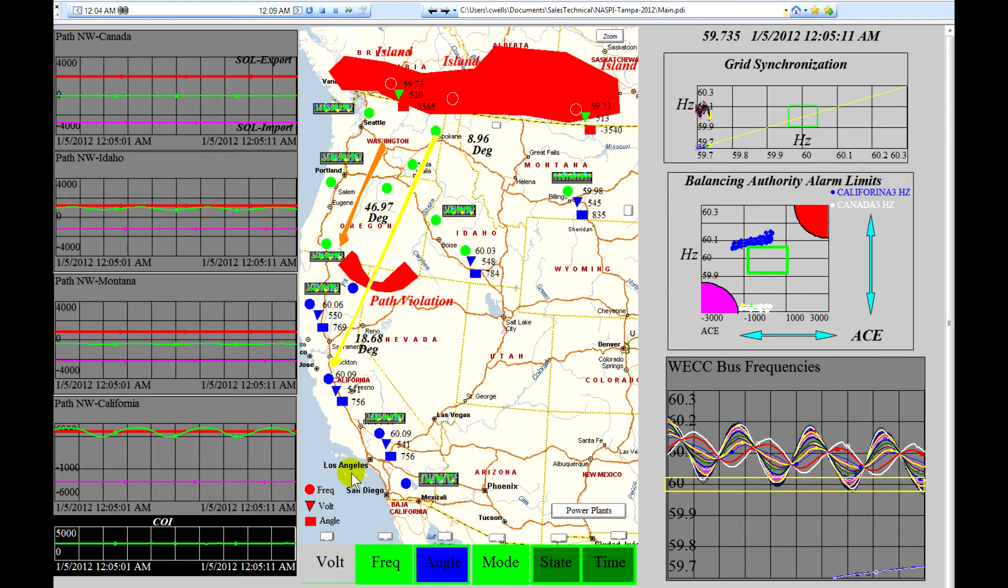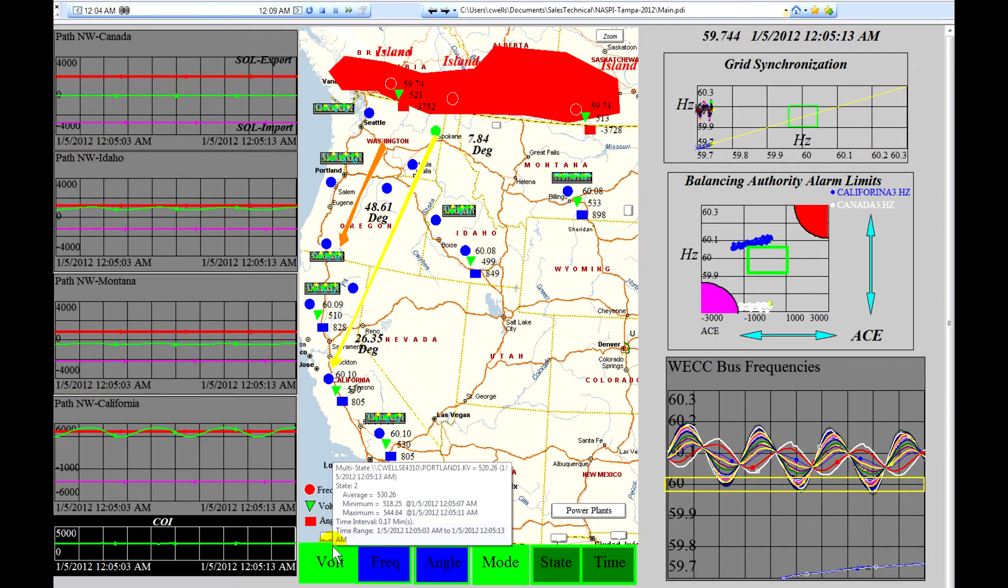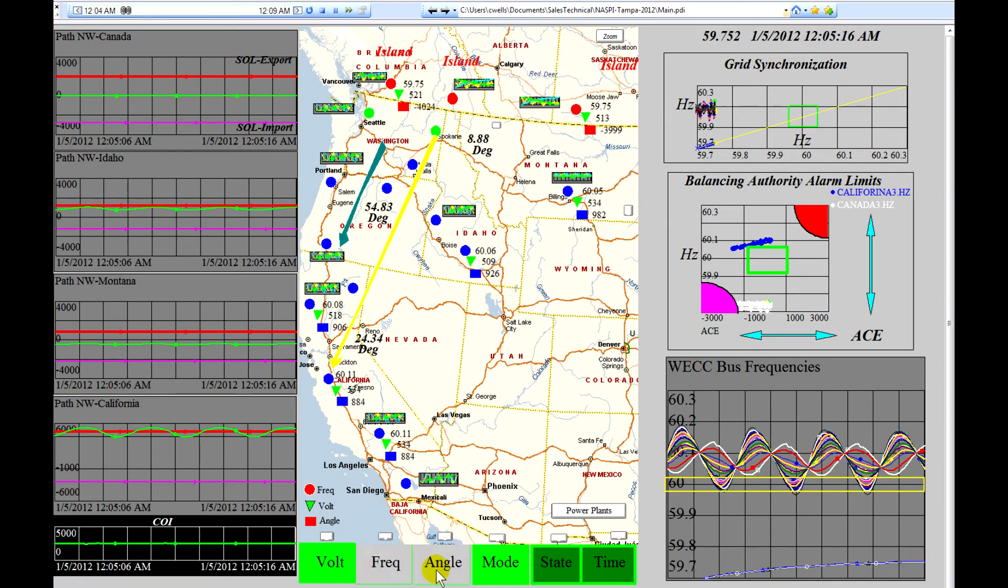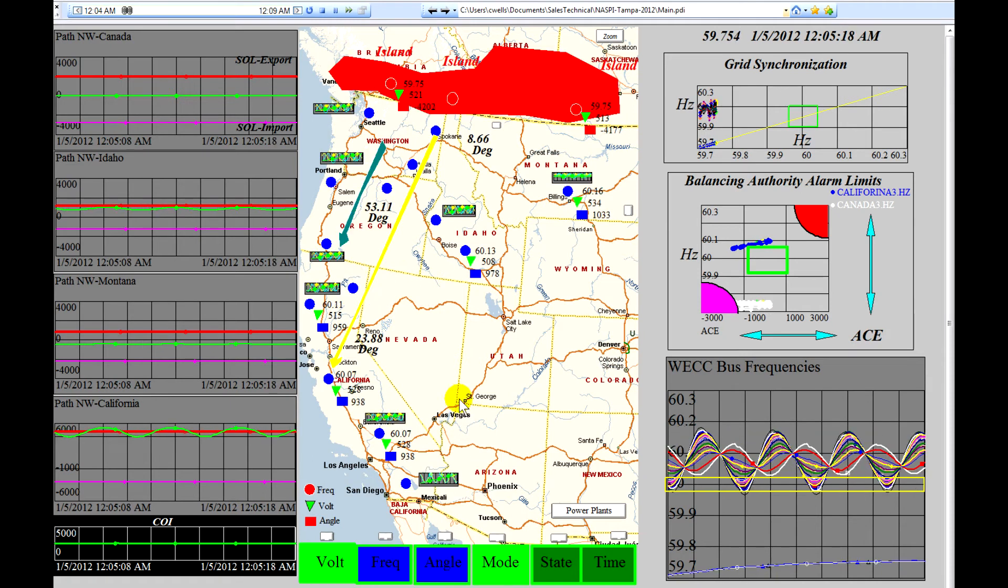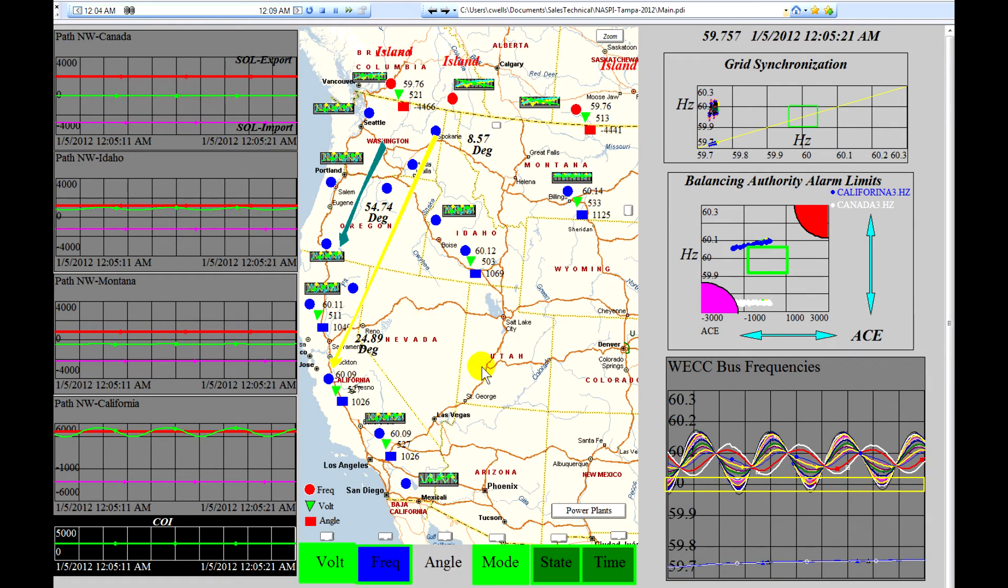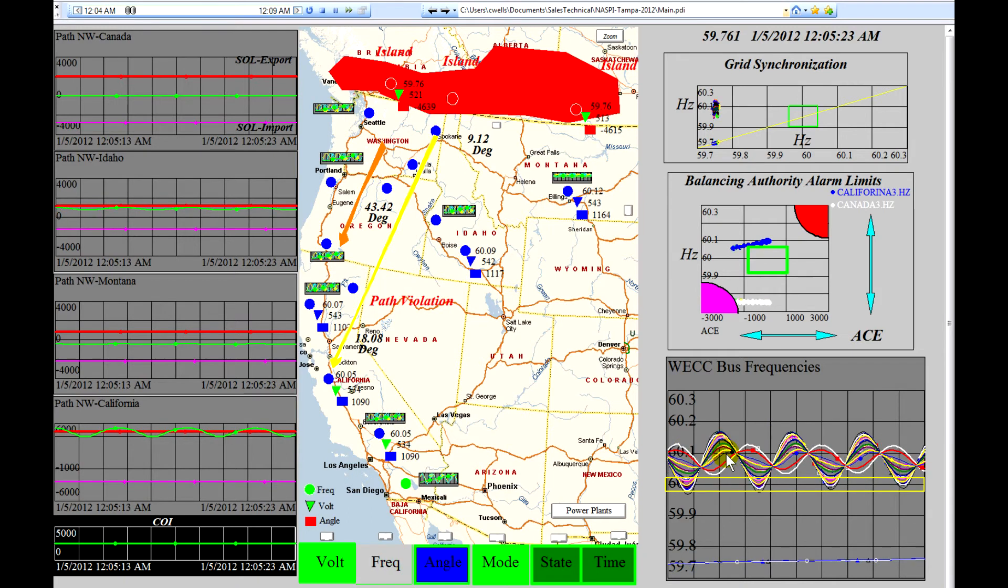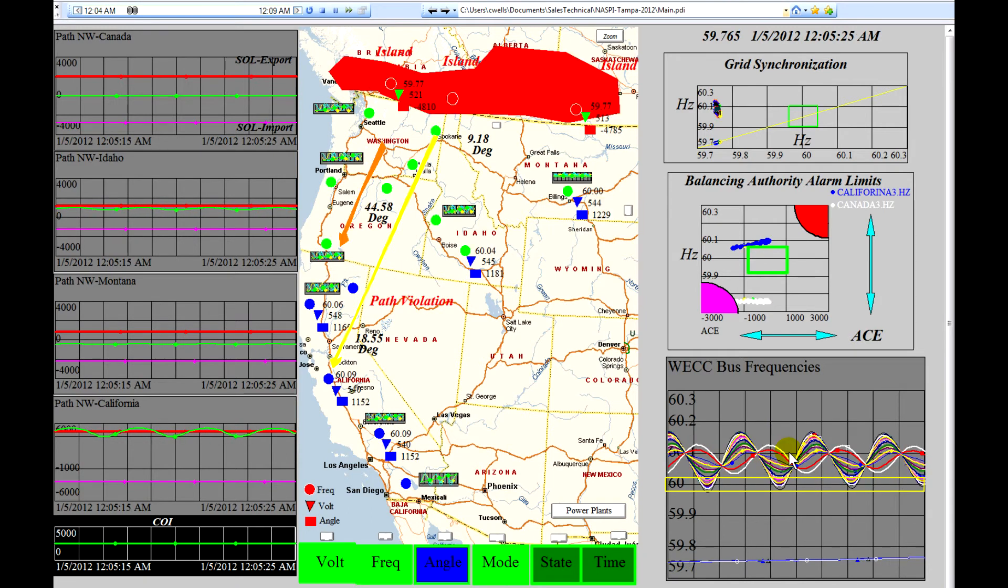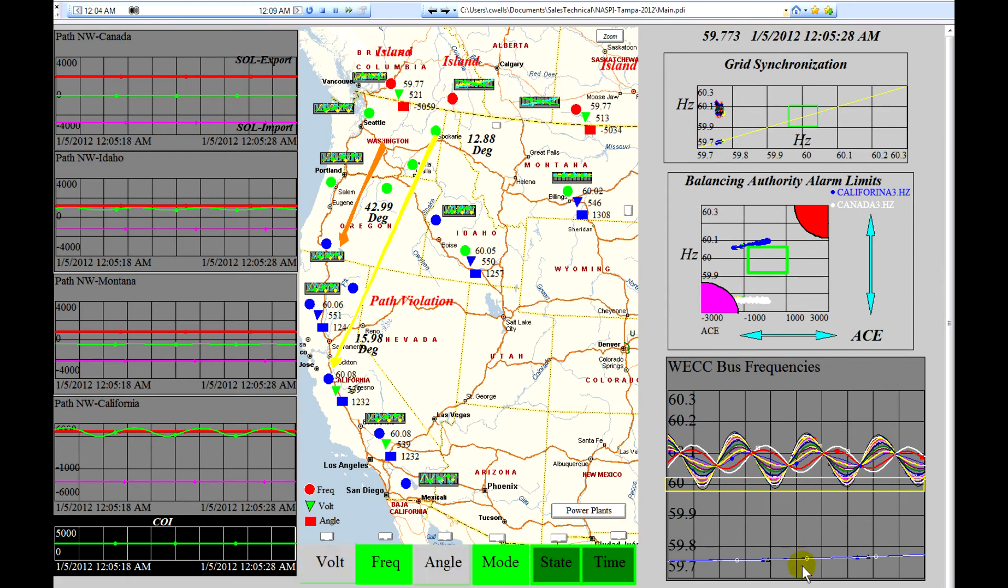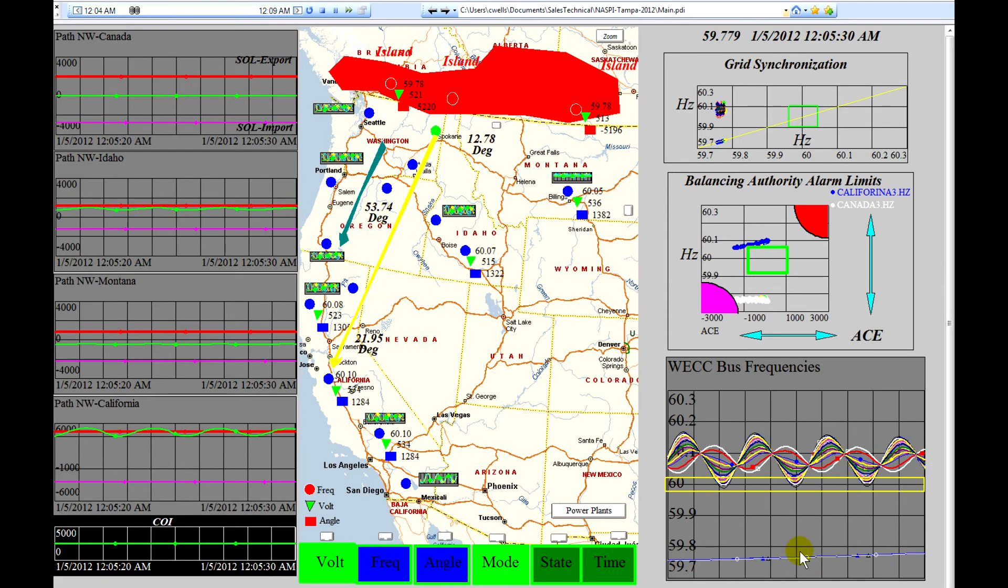We have an additional set of alarms occurring. We have frequency alarms, angle alarms, and we have path violation alarms. We'll take a look and we'll see that the frequencies in the United States are running far above 60 hertz and the frequencies in Canada are running below 60 hertz.